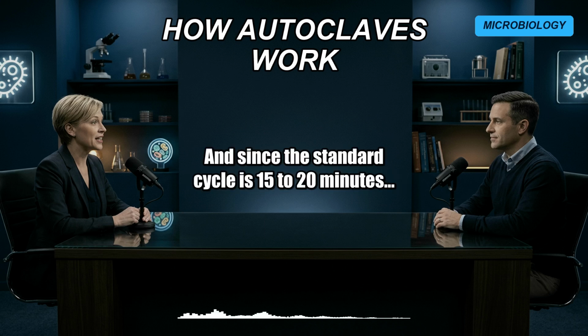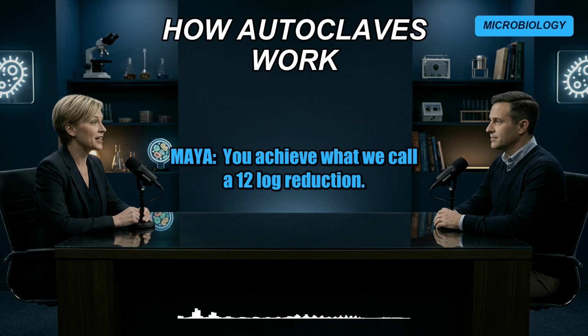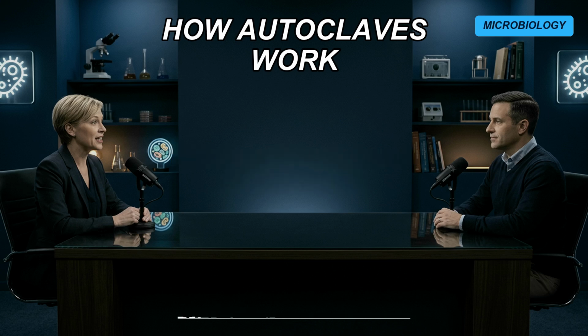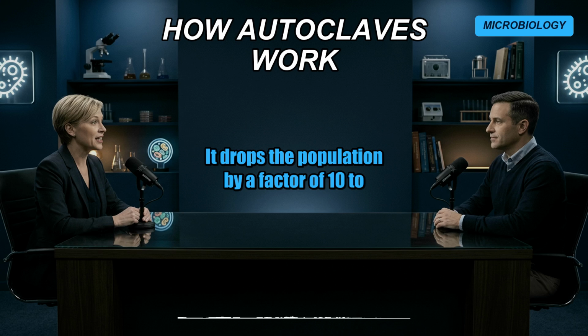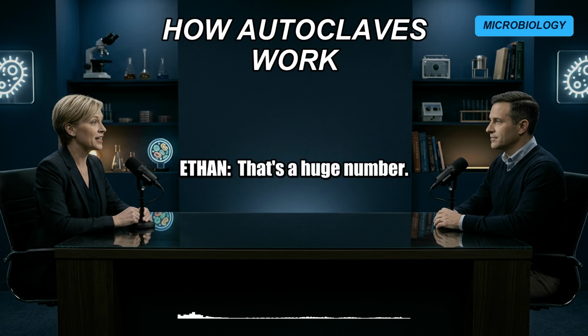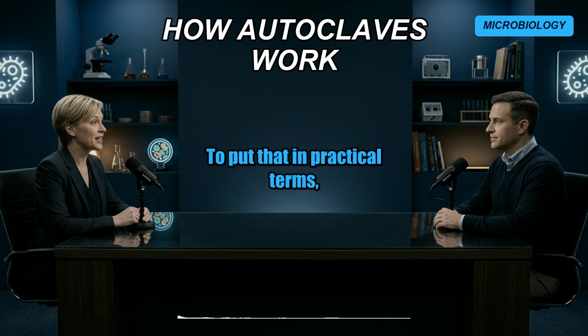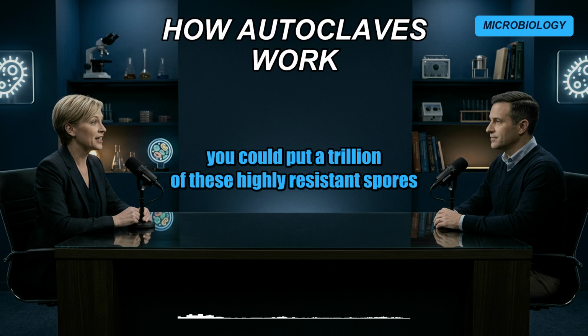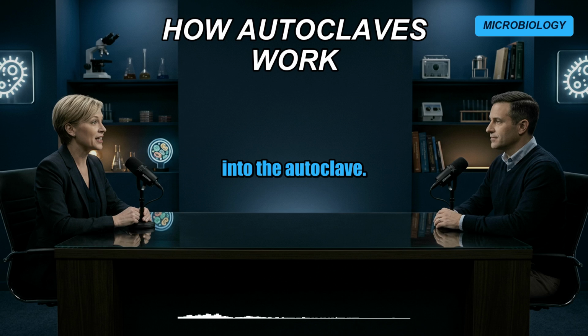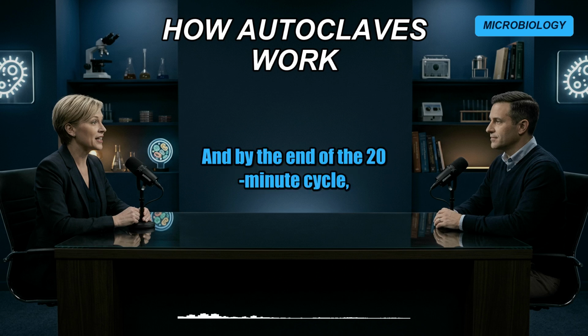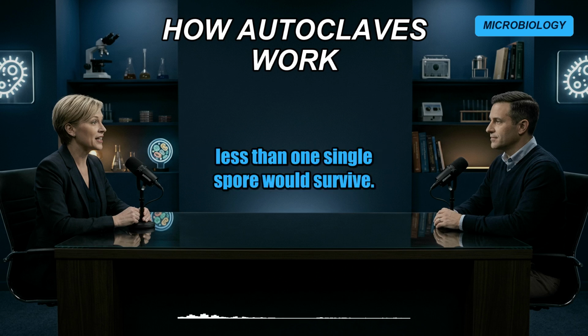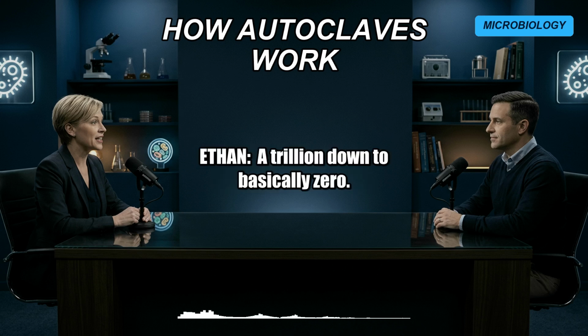And since the standard cycle is 15 to 20 minutes. You achieve what we call a 12-log reduction. It drops the population by a factor of 10 to the 12th power. That's a huge number. It is. To put that in practical terms, you could put 1 trillion of these highly resistant spores into the autoclave, and by the end of the 20-minute cycle, statistically, less than 1 single spore would survive. 1 trillion down to basically 0.